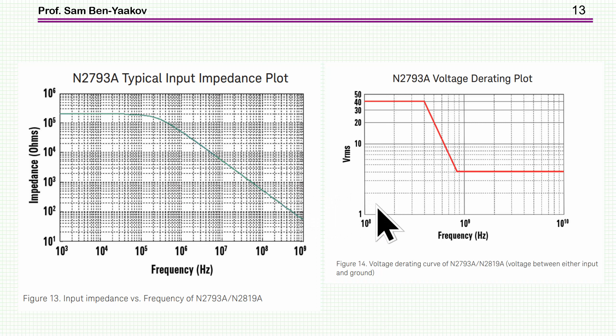The reason is that at high frequency, the impedance is very low, relatively speaking, maybe 100 ohms or hundreds of ohms. If the voltage is high, you'll get a very high current, and this will harm the components. So the current is actually limiting the voltage you can expose the probe to at high frequency.